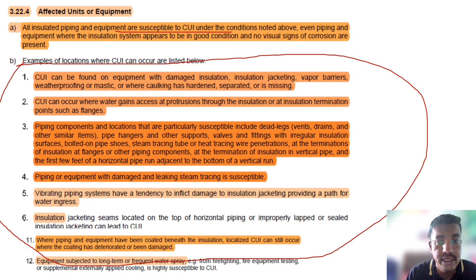Prevention, how you can do that? Since most construction materials used in refining are susceptible to CUI damage, mitigation is best achieved by applying an appropriate coating to the equipment prior to the insulation. So if this is the piping and you have to do the insulation on top of it, before doing the insulation you can put a coating layer on top of the pipe. So even though there is any ingress of water from outside or there is a leak from inside, the water will not damage the whole surface. A small surface will be damaged and we can find it out during our routine inspection. So inspection and monitoring, how will we do that?